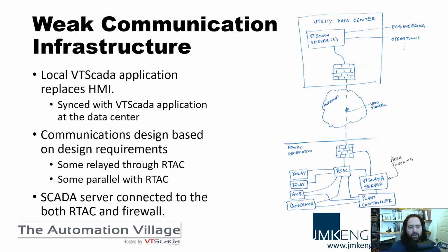The way this is set up is similar to what I've done for a previous client who owns small generation assets throughout Atlantic Canada. One of their assets is a small plant in remote Labrador, and they have poor communication. So we wanted to make sure we don't lose any information over time, but that the client still has a single place they can log on and view all of the other sites. So we have a master application in their headquarters, with VT SCADA servers, sometimes two, with all their assets.